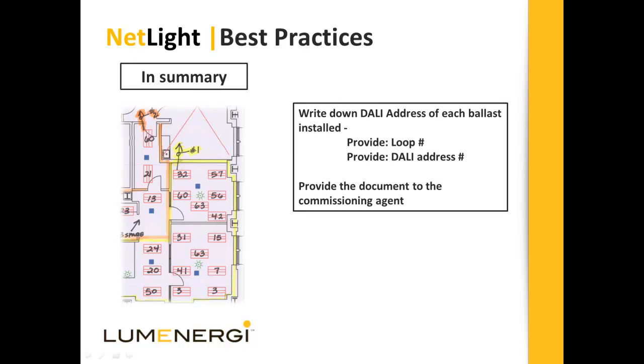While installing the fixtures in the ceiling, write down the DALI loop number and address of the fixture on the reflected ceiling plan to inform the commissioning agent of the correct address location. Once completed, provide this document to Lumenergi's assigned commissioning agent.